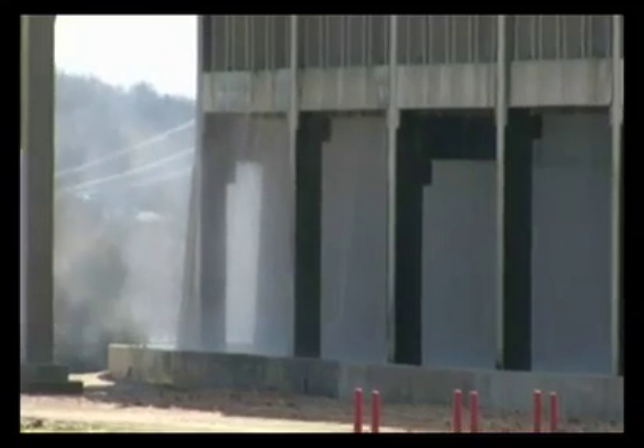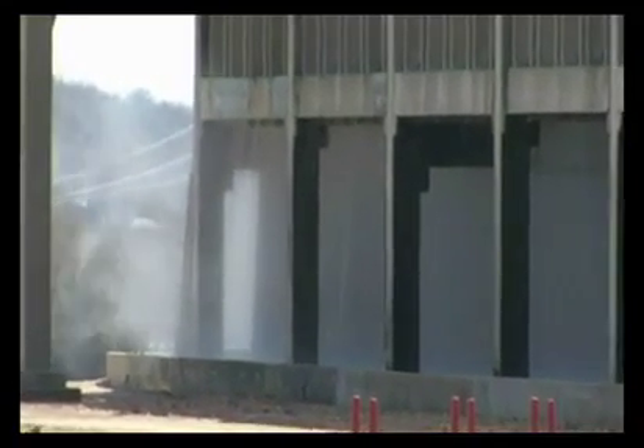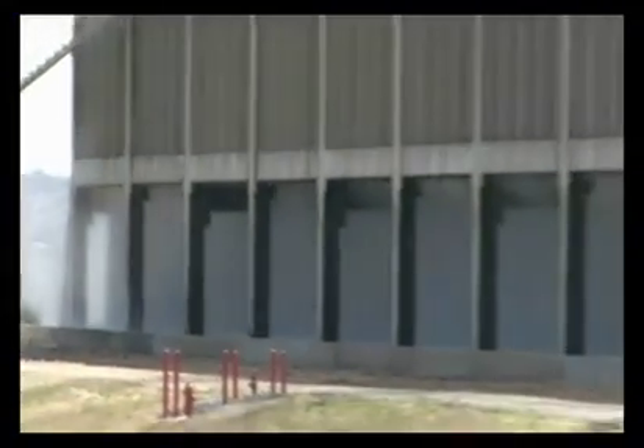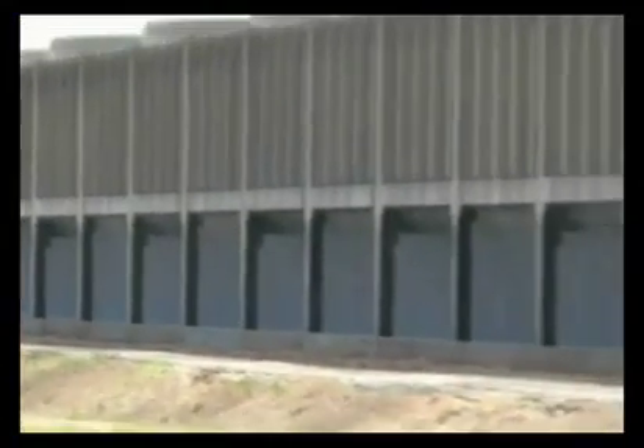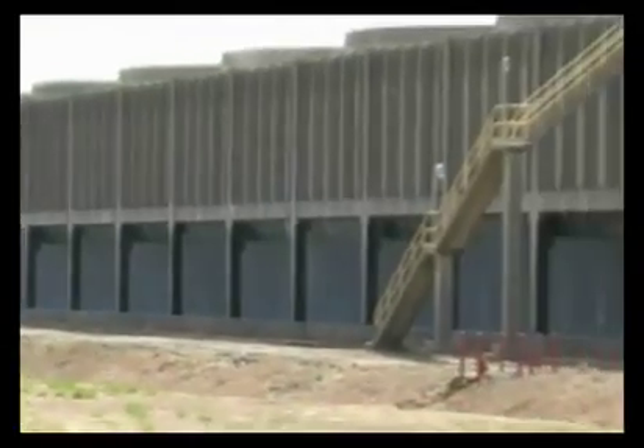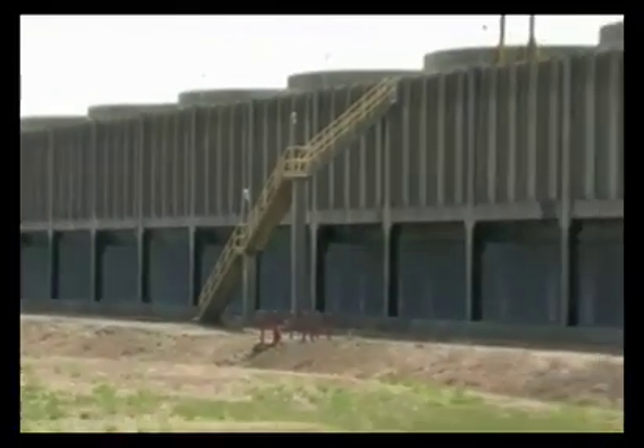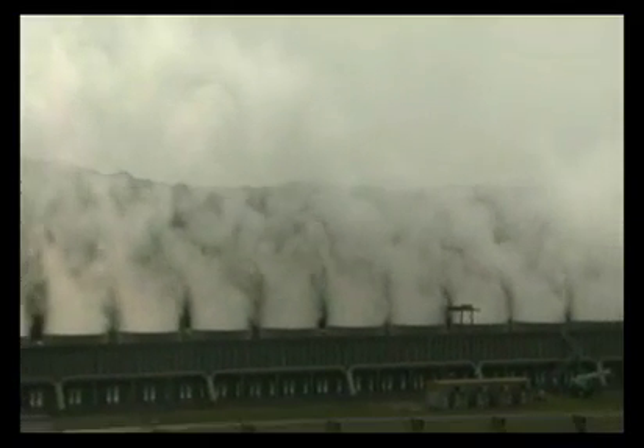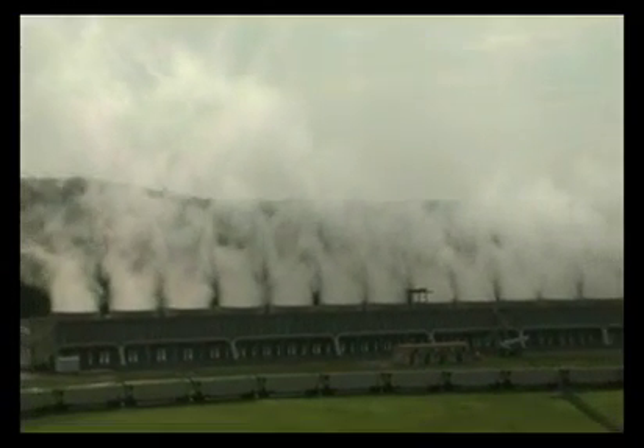After the steam drives the turbine, it is piped to a condenser which consists of tubes full of cool water. As the steam touches the tubes, it condenses back into water. Then it is sent to the cooling towers where its temperature is lowered before it is returned to the boiler to start the cycle again. In fact, the cloud-like plume coming from the cooling towers in front of the plant is merely water vapor from this cooling process.